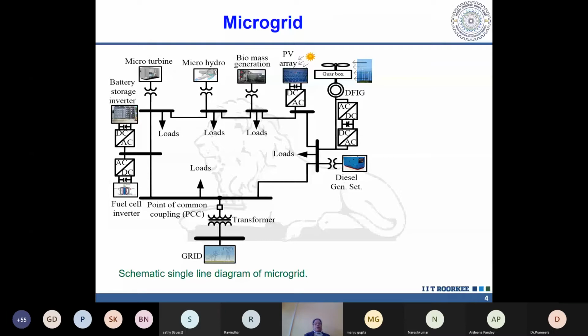When the grid is connected, this is known as the grid side circuit breaker and grid side connecting transformer, the main transformer, which steps up, or sometimes steps down. If my grid is 33 kV and this particular mesh network is 11 kV, this transformer will be a step down transformer, stepping down the 33 kV voltage level to the 11 kV voltage level.